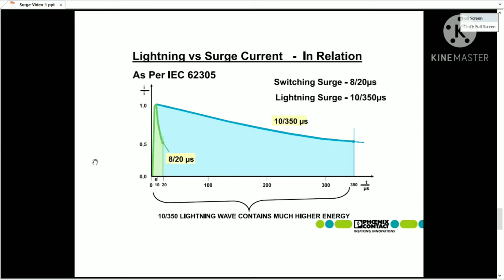A lightning surge typically lasts for 350 microseconds and achieves its maximum amplitude in the first 10 microseconds, whereas the switching surge lasts for just 20 microseconds but achieves the same amplitude in the first 8 microseconds. It is the longer duration of the lightning surge which causes more damage. Lightning and a switching surge. This large area represents the 10 by 350 microseconds lightning surge, and this smaller area within represents the 8 by 20 microseconds switching surge. You can see that both these surges attain the same maximum amplitude. However, it is the longer duration of the lightning surge which is the cause of greater damage.